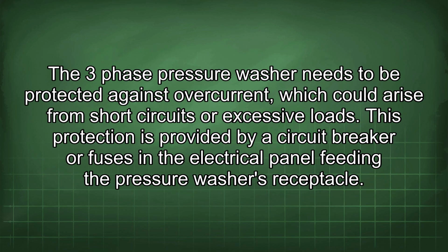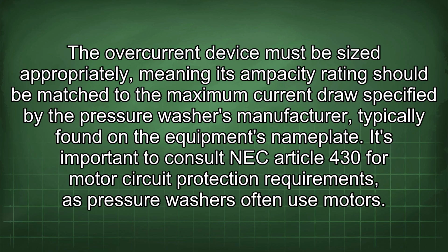Secondly, circuit protection is a must for any electrical equipment. The three-phase pressure washer needs to be protected against overcurrent, which could arise from short circuits or excessive loads. This protection is provided by a circuit breaker or fuses in the electrical panel feeding the pressure washer's receptacle. The overcurrent device must be sized appropriately, meaning its ampacity rating should be matched to the maximum current draw specified by the pressure washer's manufacturer, typically found on the equipment's nameplate. It's important to consult NEC Article 430 for motor circuit protection requirements, as pressure washers often use motors.